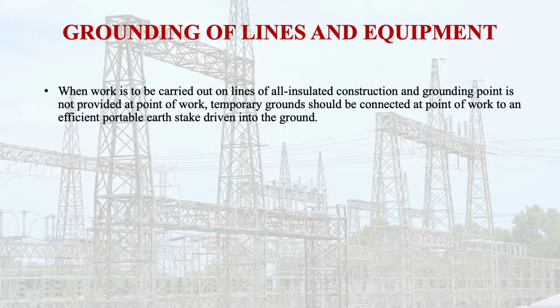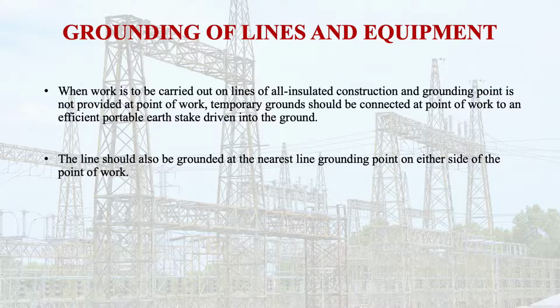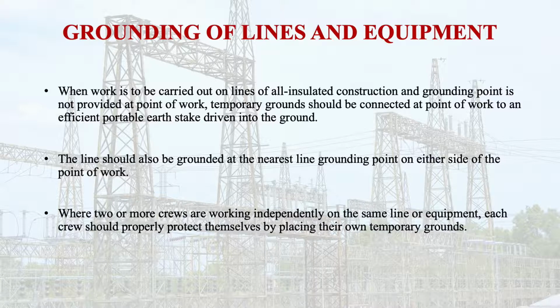So when work is to be carried out on lines of all insulated construction and grounding points are not provided at the point of work, temporary ground should be connected at the point of work to an efficient portable earth stake driven into the ground. The line should also be grounded at the nearest line grounding point on either side of the point of work. Where 2 or more crews are working independently on the same line or equipment, each crew should properly protect themselves by placing their own temporary grounds.